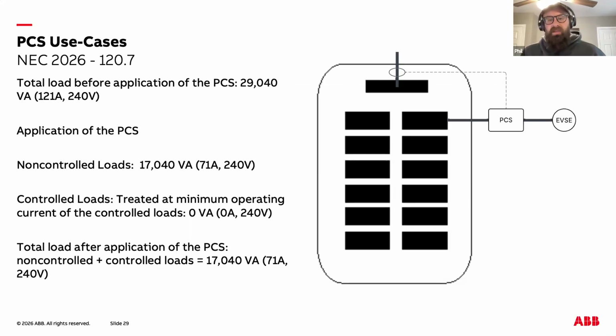In this scenario, the EVSE has a nameplate rating of 12,000 volt-amperes, and it is placed under the control of a power control system. The PCS is programmed to monitor the service conductors and automatically adjust the EVSE's demand whenever the total service load approaches the PCS control limit. Because the EVSE can be reduced all the way down to 0 output, its minimum operating current is 0 amps, which becomes important for load calculation purposes.